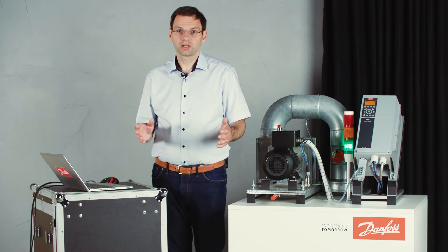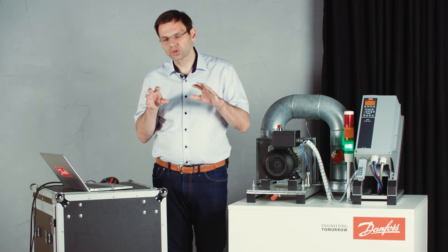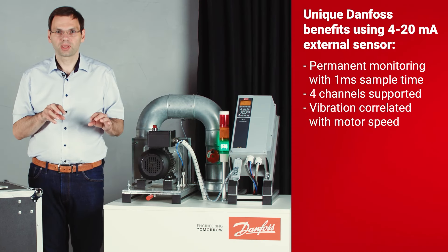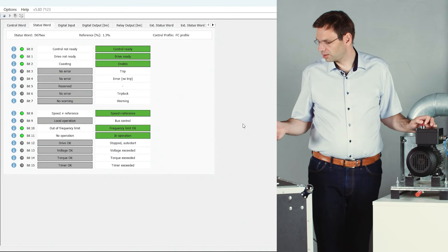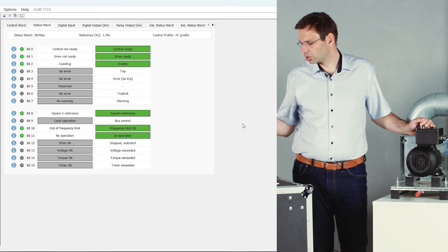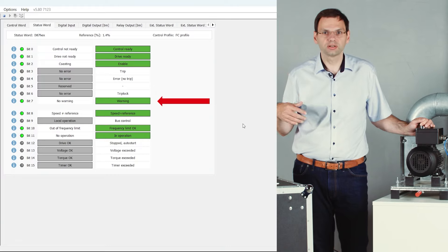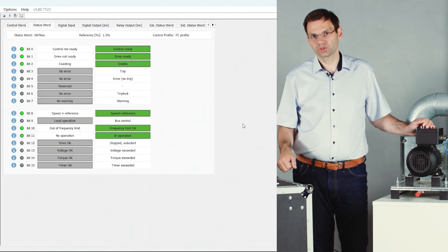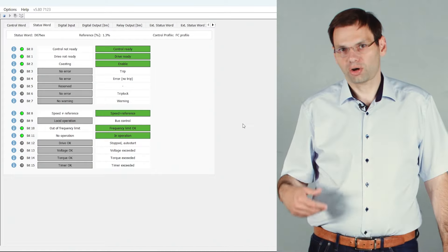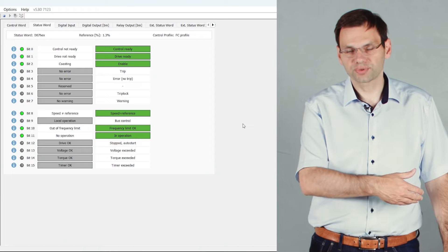Vibration monitoring is very relevant in variable speed applications because you can monitor the vibration level at different speeds. If you run variable speed, you can have mechanical resonances, and these can be taken into consideration. The integration of condition monitoring in an automation system is quite easy — all faults are represented in the status word of the drive. I create a fault and you can see the warning bit turns to one, meaning a PLC or automation system can detect the warning and notify the user.